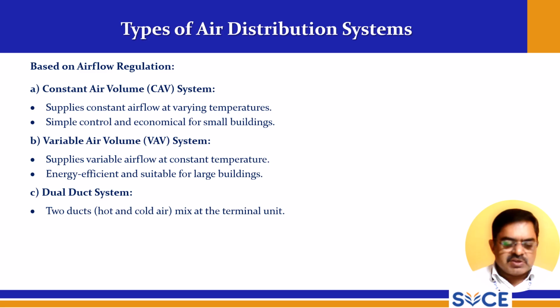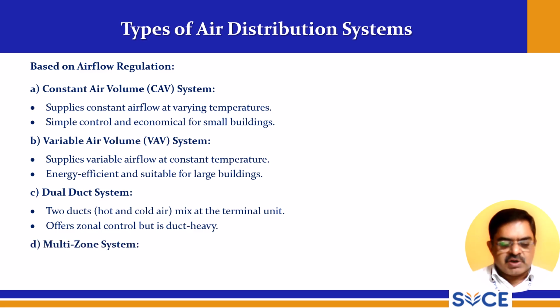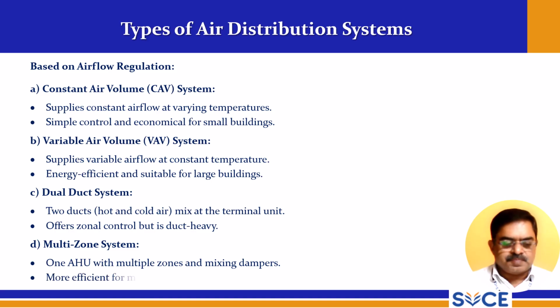Dual duct systems: two ducts, where hot and cold air mix at the terminal unit. It offers zonal control, but is duct heavy, because two ducts are used. Multi-zone system: one AHU, air handling unit, with multiple zones and mixing dampers, more efficient for mid-sized applications.